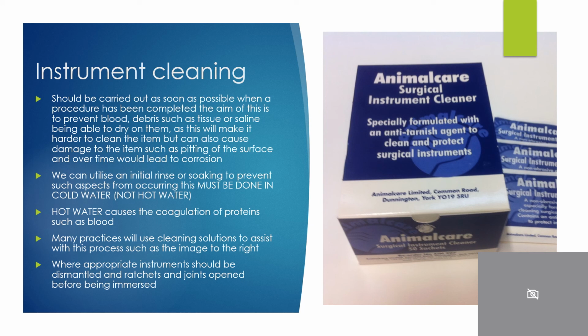We can utilise initial rinse or soaking to prevent such aspects from occurring, and this must be done in cold water, not hot water. Hot water causes the coagulation of proteins such as blood. Many practices will use solutions to assist with this process, such as the image to the right, where appropriate instruments should be dismantled and ratchets and joints opened before being immersed.